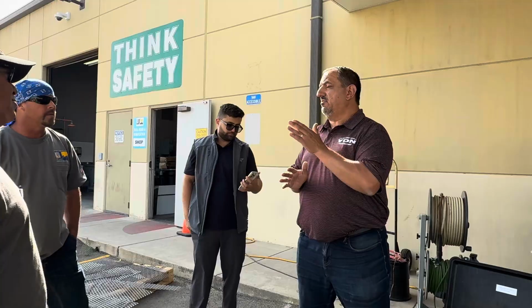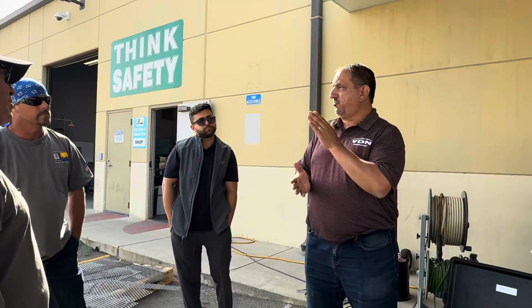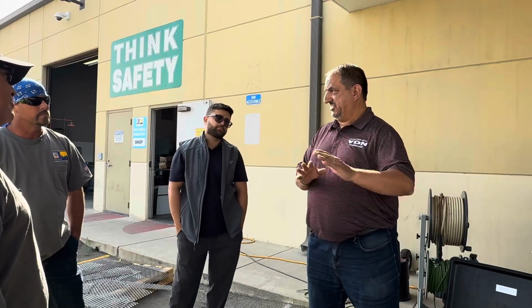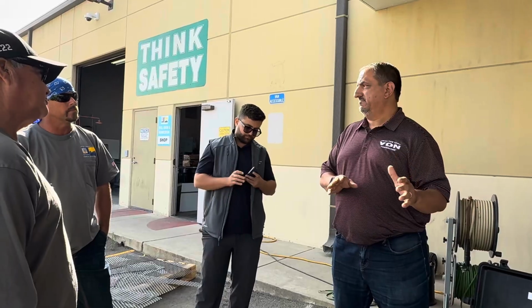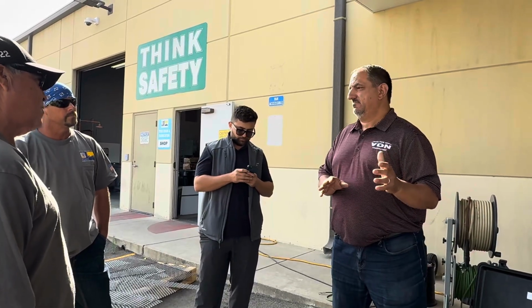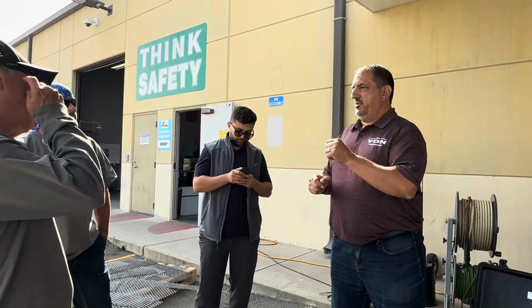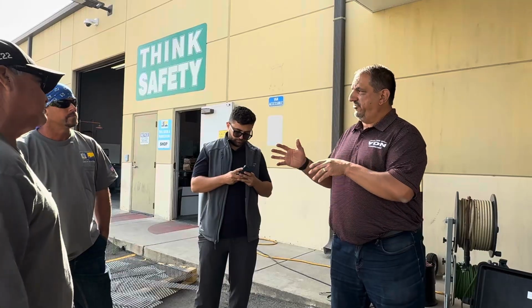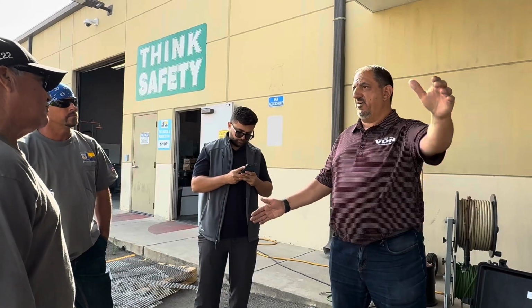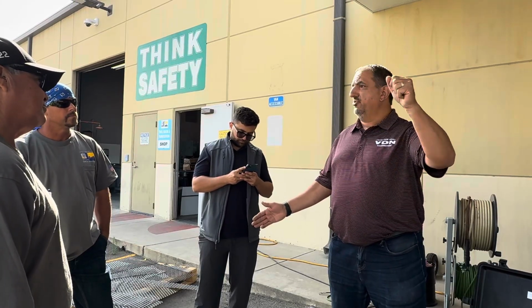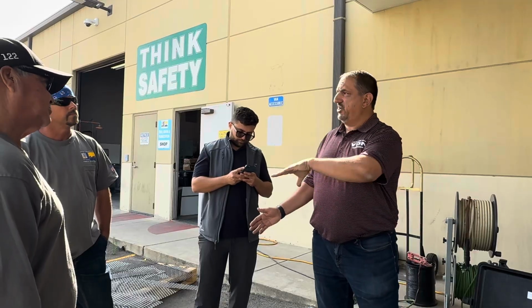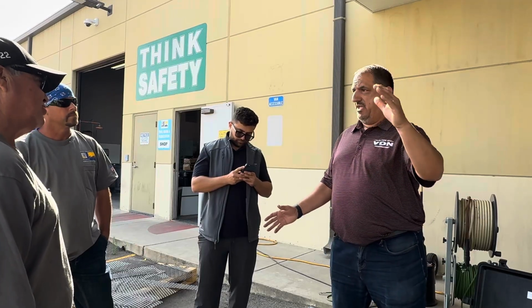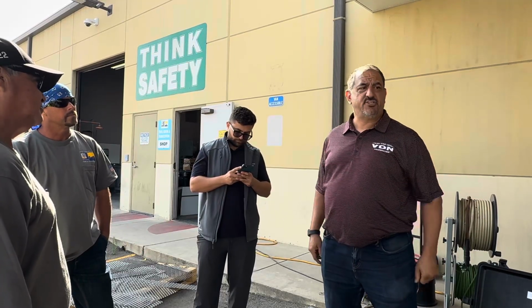If you were to cut the cable and just leave it, technically that's a fault. So here's the question: you have a cable with a fault here, and the other end where you just cut it and didn't do anything else, didn't peel the conductor or the semicon, just left it there. That's another fault. Which fault is going to show up first?